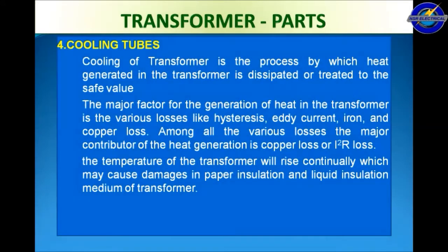Fourth one is cooling tubes or radiators. Cooling of a transformer is the process by which heat generated in the transformer is dissipated to a safe value. The major factor for the generation of heat in the transformer is various losses like hysteresis, eddy current, iron and copper losses. Among all the various losses, the major contributor of heat generation is copper losses, I square R losses. The temperature of the transformer will rise continuously, which may cause damage to the paper insulation or liquid insulation medium of transformers.